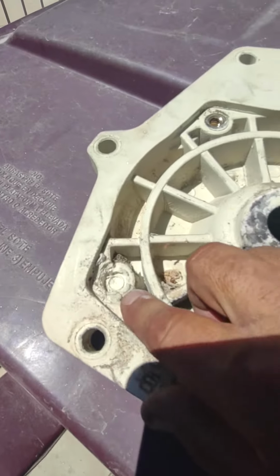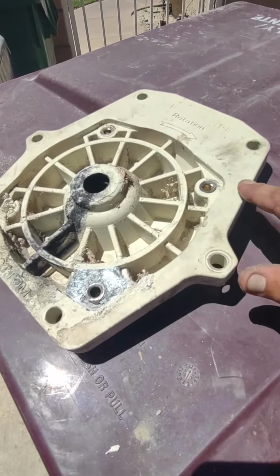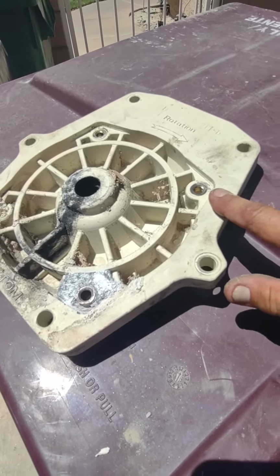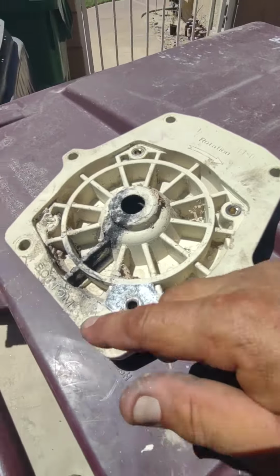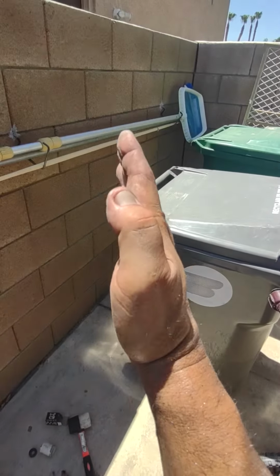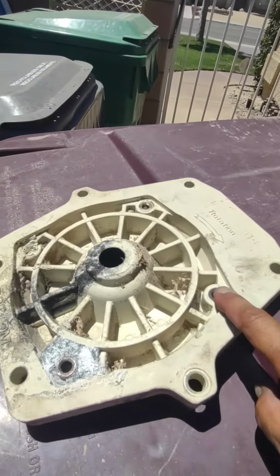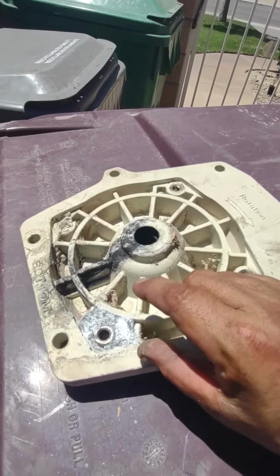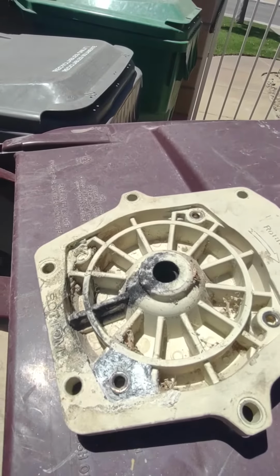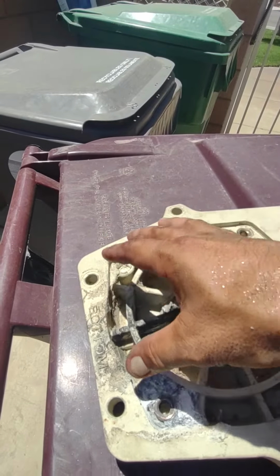Okay. So if you look close enough, when the motor's attached, and you look at the flange attached, there is a thinner gap, and then you see that it kind of pops out like this, right? Just a little bit. So in the top, it goes like this, and then you see it get a little bit bigger, probably about 1/8 to 1/4 inch wider down here, because it's pulling away.